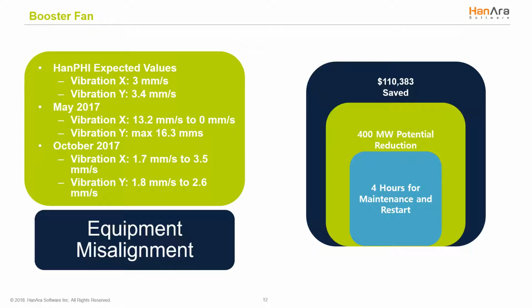But on October 7, HanPHI identified booster fan vibration hunting. Vibration X increased from 1.7 millimeters per second to 3.5 millimeters per second, and vibration Y increased from 1.8 millimeters per second to 2.6 millimeters per second, while fan inboard vibrations remained normal. At this moment, the site confirmed equipment misalignment and acted.